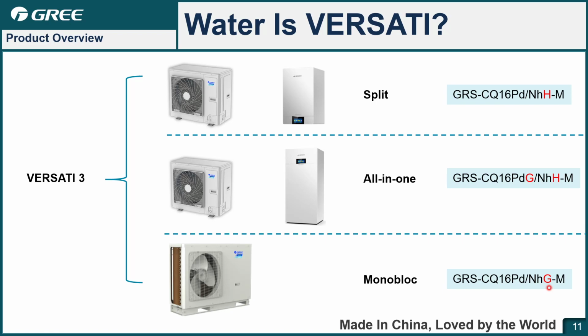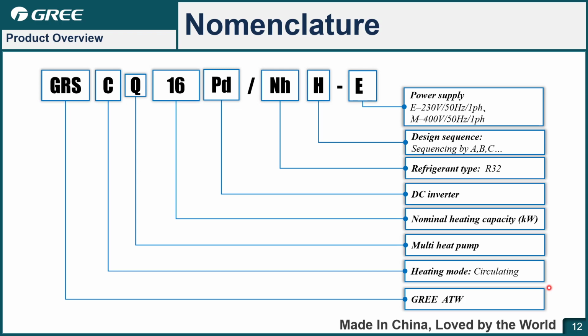Now we have a general view of the product lineup. Here is the nomenclature of split. GRS means hot water, C is circulating type, and Q is the heat pump. Here is the capacity, and PD means DC inverter. NH is the refrigerant type, R32. Here is the design sequence code, A, B, C, D, etc. For the VERSATI 3, split is H. Then the last part is the power supply. We have single phase and 3-phase power supply to choose from.